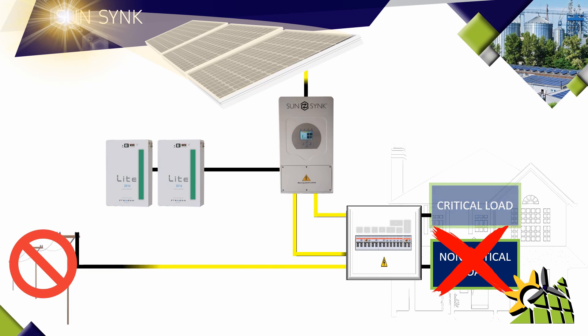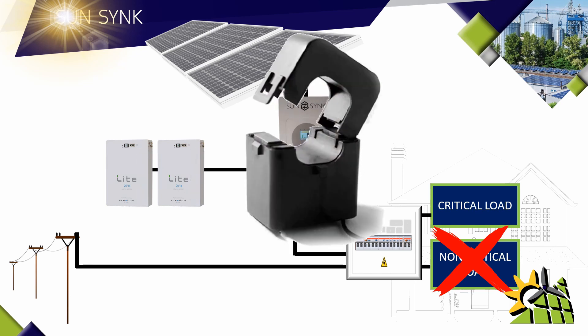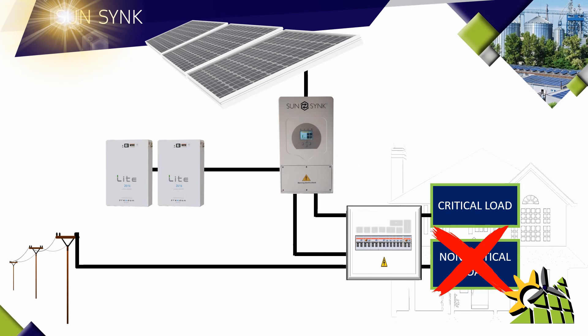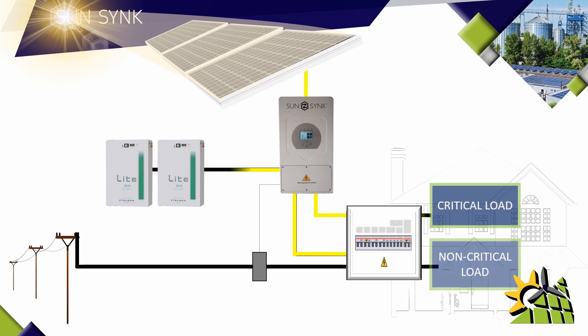The problem is this may not be allowed by certain municipalities, but there is an easy solution in the form of a CT. The CT can be connected to the input line of the inverter or the input line from the grid, and it will communicate with the SunSynk inverter. If there is additional power produced by the solar panels that is not being consumed by the non-critical load, the CT will simply prevent that power from being fed back into the grid. If an appliance in the non-critical load is then switched on, the SunSynk inverter will automatically direct that power to the non-critical load and not draw it from the grid.